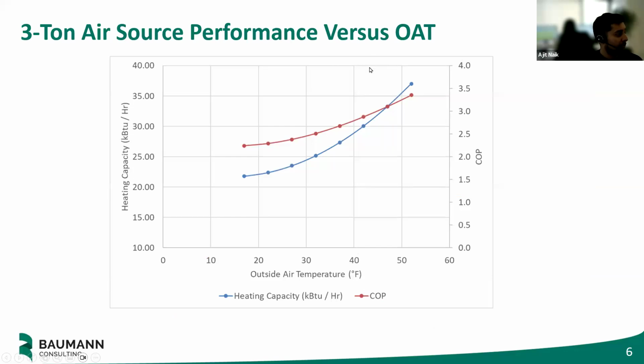However, as mentioned, not only does the efficiency drop with temperature, but also the capacity. So what we're looking at here is a 3-ton air source heat pump and its performance versus OAT, which is outside air temperature. The efficiency is this red line, and the capacity, how much heat it physically can put out, is the blue line.